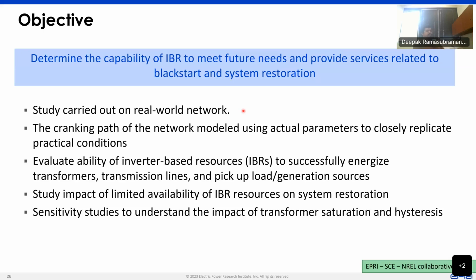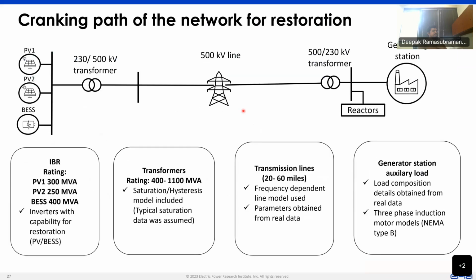It had to successfully energize transformers and transmission lines, pick up load, start up induction motors, and handle long, high-voltage transmission lines. It also looked at limited availability, because one of the topics that keeps coming up with inverter-based resources and black start is, what if the resource is not available? What if we don't have the back-end energy needed to do the black start? And is there going to be an impact on transformer saturation and hysteresis?